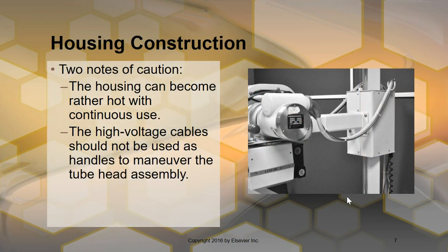Another thing about the housing construction, there's two notes of caution. If we did not have the housing and then the oil that's in it, then it would be hot every time, if we used it more often. And it's likely to occur more if there's fluoroscopy installed and if there's a permanently installed unit, which that's with fluoroscopy because they're under the table. And another reason for doing that is because if they were up top when we were doing fluoroscopy, it may be harder to keep them cool.